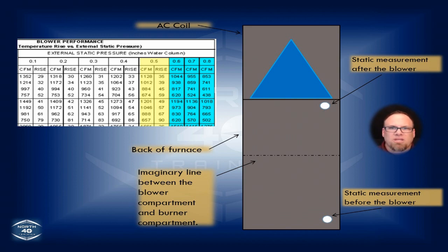Now, if you look at where the two white holes are in this furnace, they could be symbolic of the side of the furnace or the back of the furnace. You could make those two penetrations actually in different spots. I've seen people, and I myself have gone in through the high limit switch, removing the high limit switch. We're not running this on heat or cool. We're only using the fan auto speed or potentially just setting up dip switches. You could go in through the high limit switch, and I've seen people go in before the blower section with taps that go in through the low voltage side of that cabinet. So there are other places that you could go.